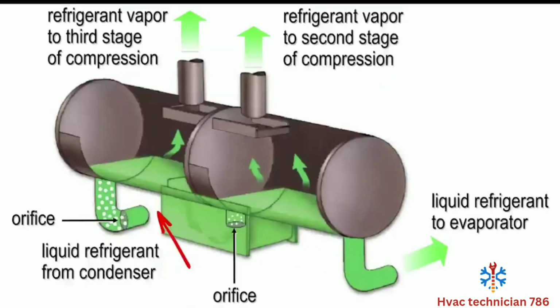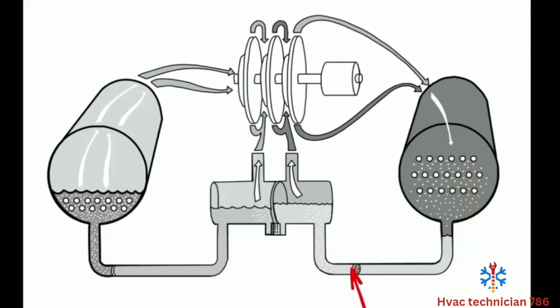Now this is a little different when we get to a CVHE series. So we're going to pull liquid in from the condenser. That high pressure liquid is converting to a medium pressure saturated refrigerant up in here, and into our first chamber. In this first pressure drop chamber, we will go to a medium pressure, but it's a little bit higher pressure than we saw in the CVHF design. And this is going to pull up into our third stage impeller. We can see here coming out of the condenser, we hit the flash plate, we come up, and then we pull into our third stage. This is our final stage of the compressor cycle before it gets pushed back into the condenser. So both of these chambers are considered a medium pressure at this point, but it's still a higher pressure.